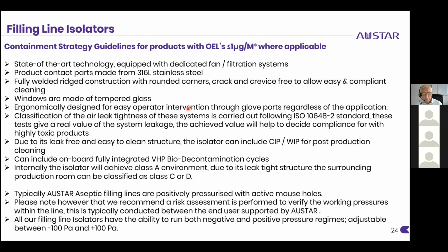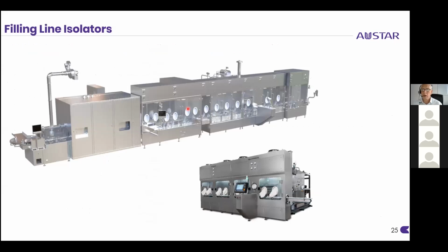We can have them positive or negative pressure. It's dependent on the end user and the risk assessment. And that's what a filling line isolator looks like. They are big isolators sat on top of large filling lines.